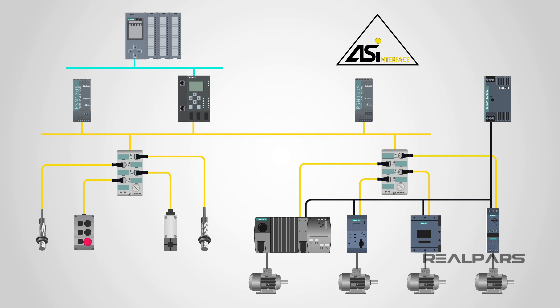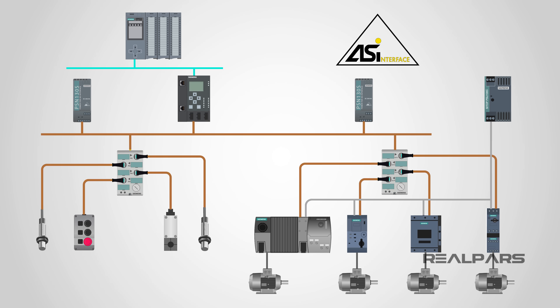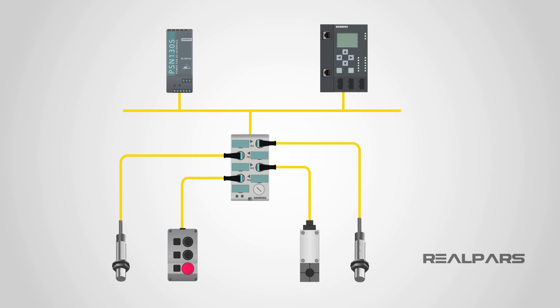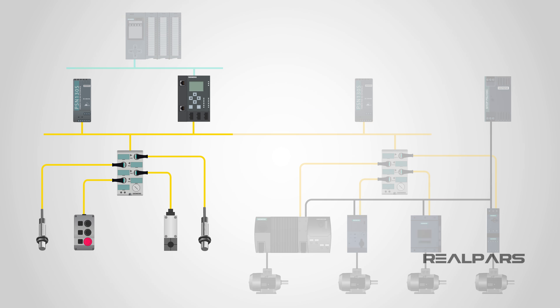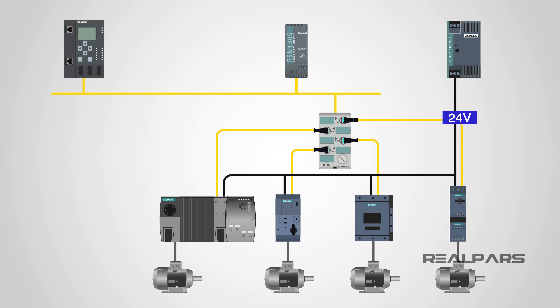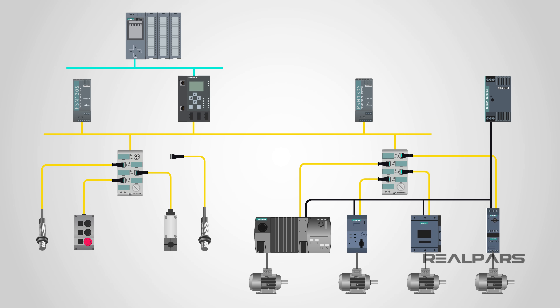Next up is the AS Interface cable. There are two cables required in an AS Interface system: a yellow cable to carry the power and data to sensors, and a black cable to carry 24 volts to actuators. There is no fiddly wiring to do though, because these use a special piercing technology, which means that the nodes can be literally snapped onto the cable at any point.